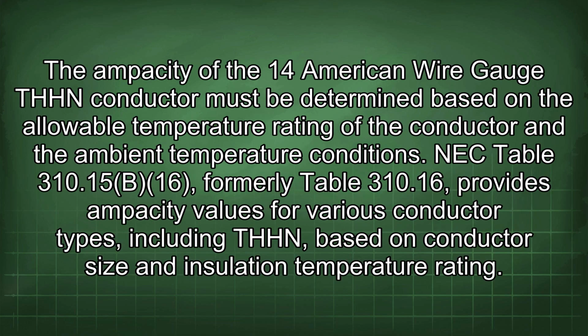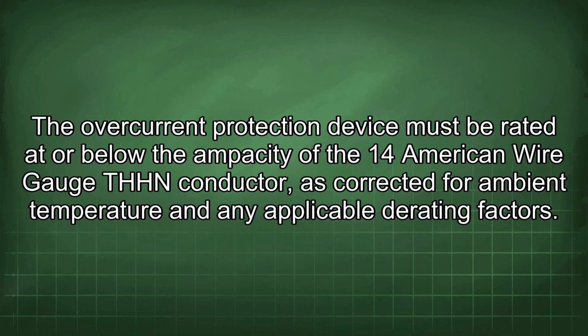The ampacity of the 14 American wire gauge THHN conductor must be determined based on the allowable temperature rating of the conductor and the ambient temperature conditions. NEC Table 310.15(B)(16), formerly Table 310.16, provides ampacity values for various conductor types, including THHN, based on conductor size and insulation temperature rating. The overcurrent protection device must be rated at or below the ampacity of the 14 American wire gauge THHN conductor, as corrected for ambient temperature and any applicable derating factors.